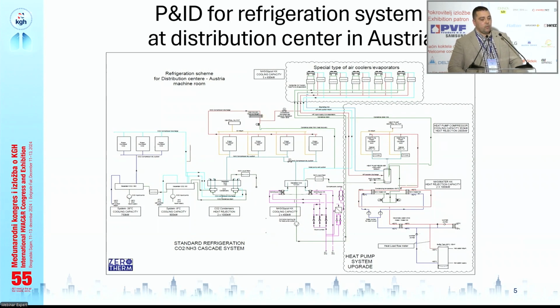Our investor requested us to install this high temperature heat pump and integrate it into the existing refrigerating system. Usually we do this with a completely independent system, but for this application, we were not able to use evaporative condensers. Rather, we installed horizontal type air coolers that can work both ways. First, as standard condensers when we have the normal refrigeration mode. And if we want to switch to heat pump mode, they work as ammonia evaporators, and they collect ambient heat from the outside and push it over the heat pump system.